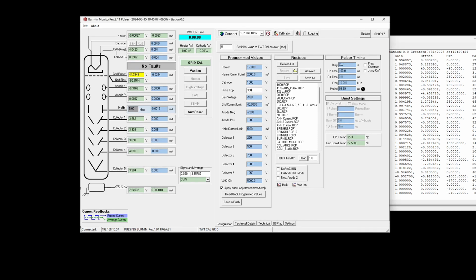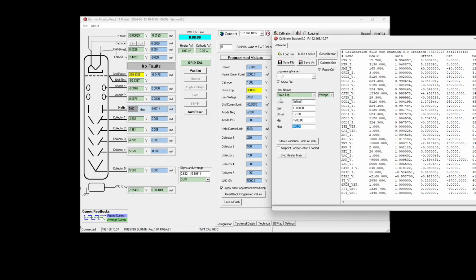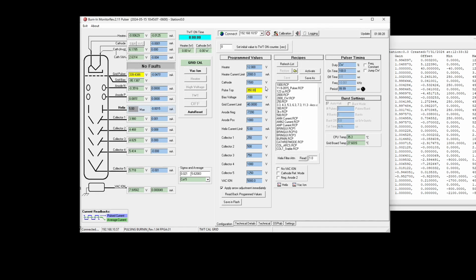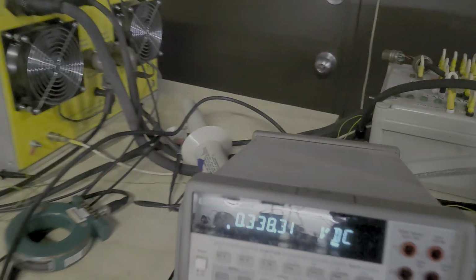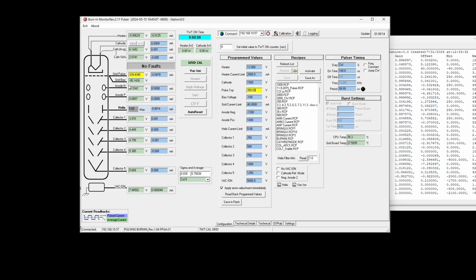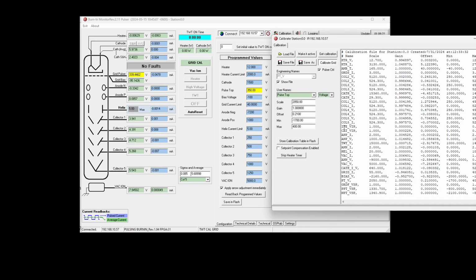Now let's boost pulse top voltage to 350. Its maximum is 400. So we'll take it to somewhere close but not quite, and this could be set by the customer to their own ideal value. I see 339.4. Let's see what the DMM says. 338.3. So 338.3 is our high end. Let's adjust gain so that we see that in the GUI. There's 6, 8, 4, and drop it a couple counts on the next digit over until we get 338.3, like so.